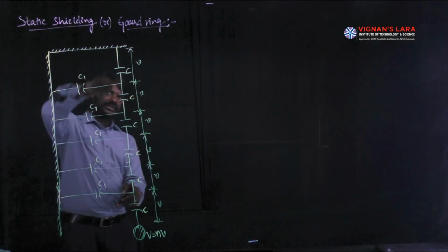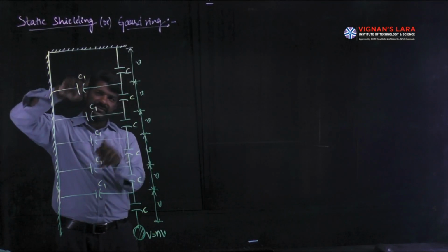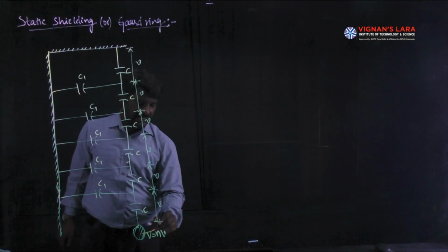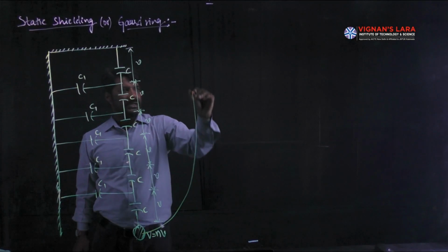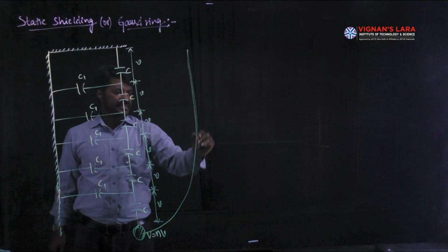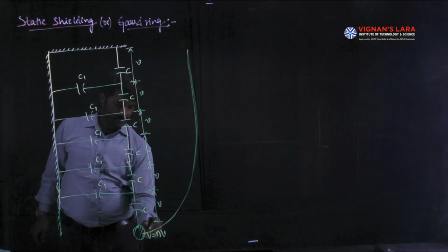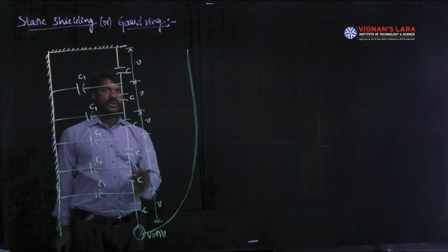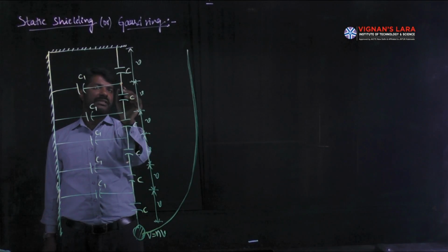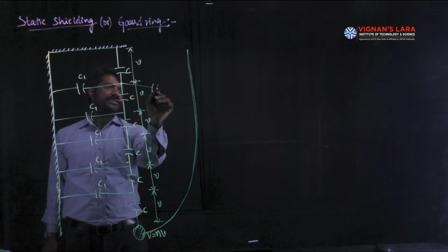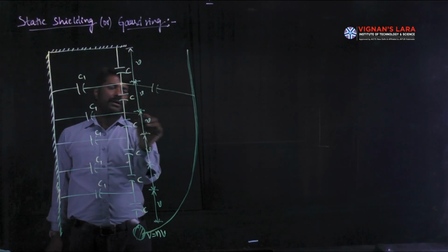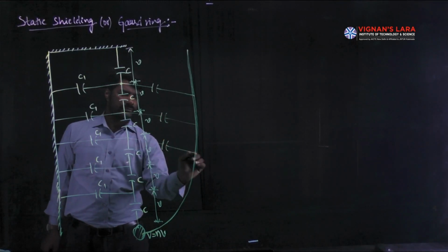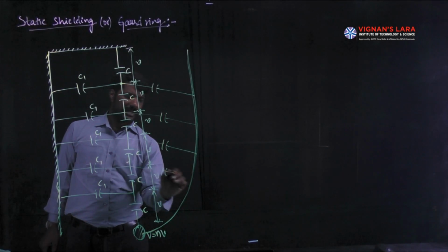In order to get the same voltages across the units even in the presence of this shunt capacitance, what we do in general is connect a shield to this live conductor, which is operated with a voltage of nV, called capital V, so that between these two at this link point, one more capacitance is observed to be formed, like this.